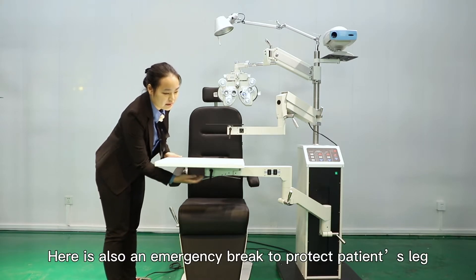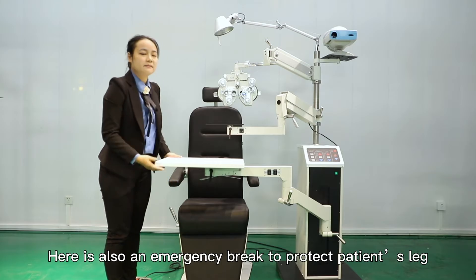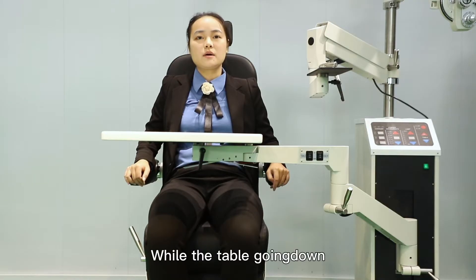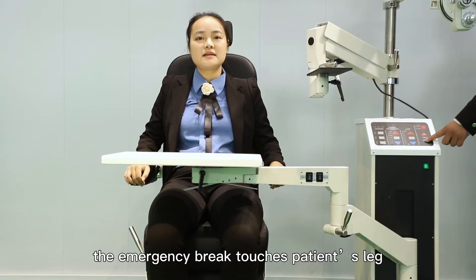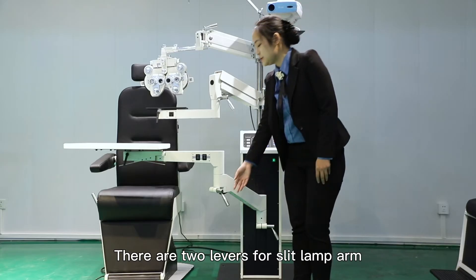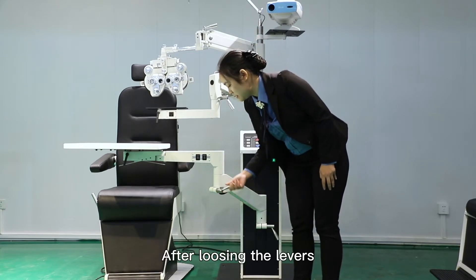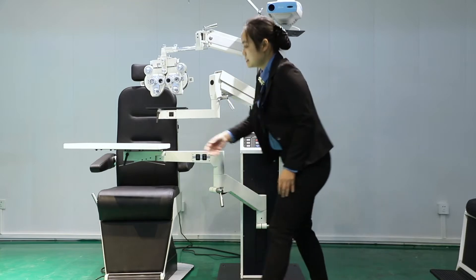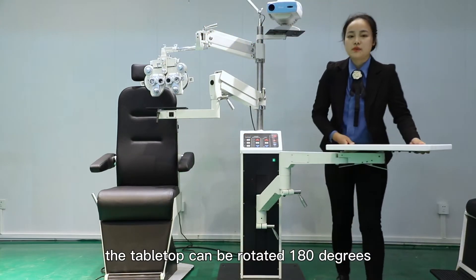Here is also an emergency brake to protect the patient's leg. While the table is going down, if the emergency brake touches the patient's leg, it will stop automatically. There are two levers for the slit lamp arm. After loosening the levers, the table can be rotated 180 degrees.